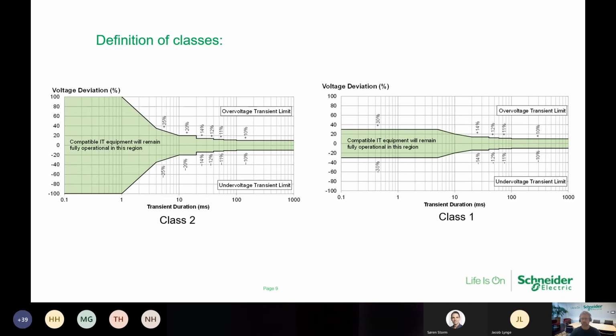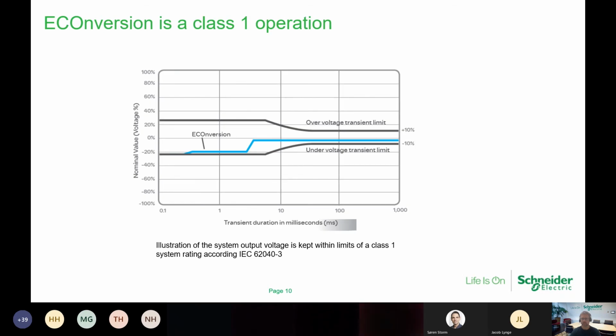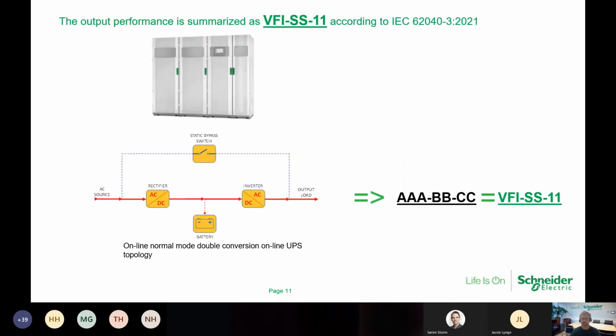As shown before, the UPS is tested according to clause 6.4, and the results show the classes the UPS complies with. On the axes we have the voltage dimension and the transient duration in milliseconds. The test result of the UPS has been added in these curves, and we can see the e-conversion mode is inside the limit of the class 1 definition according to the IEC standard 62040-3.